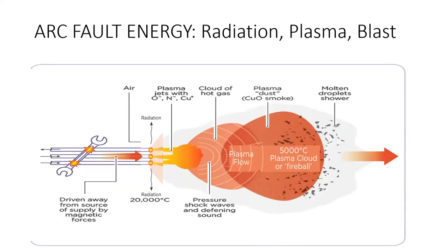So let's just look at how an arc fault leads to an arc flash. So we can see over here that the spanner has been dropped on the bus bars in the switchboard. The air ionizes at this point, the spanner will vaporize, and the arc travels away from its source due to motoring action. The arc, when it reaches the end of the bus bar, radiates the full spectrum of electromagnetic waves, including blinding light and heat to a temperature of 20,000 degrees C, which is just unthinkable, but that's hotter than the surface of the sun. The arc then liberates a deafening shockwave at something like 13 megapascals, and a plasma ball is released, which is considered to be the largest risk of injury and damage.